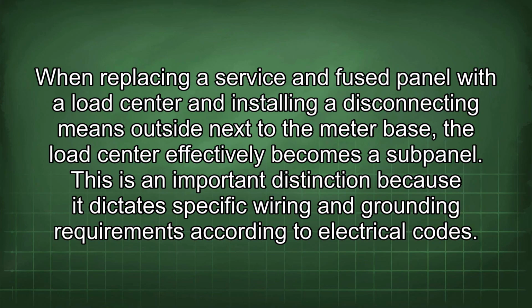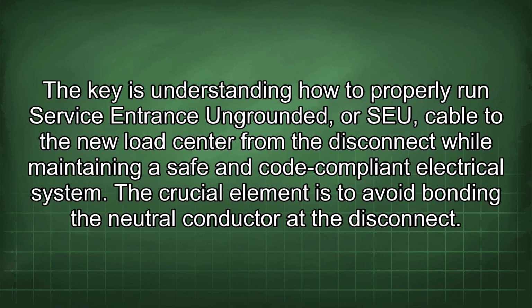When replacing a service and fuse panel with a load center and installing a disconnecting means outside next to the meter base, the load center effectively becomes a subpanel. This is an important distinction because it dictates specific wiring and grounding requirements according to electrical codes. The key is understanding how to properly run service entrance and grounded, or SEU, cable to the new load center from the disconnect while maintaining a safe and code-compliant electrical system.